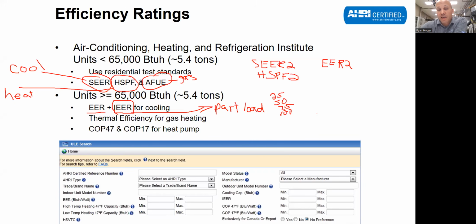They load the machine in that way with those kind of conditions, and then they put a weighted average on there, significantly weighting the middle two, and barely putting any weight on the other ones. Like 2% of it goes on here. I want to say 12% of it goes on here, and everything else goes on the middle two. So basically, it's a way to see how efficient it is in part load. A lot of utility rebates, and in some cases even municipal codes now only look at IEER and not EER.